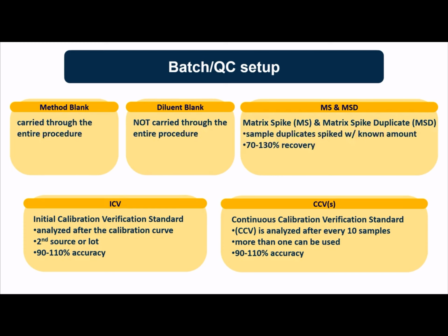So method blank, that's just simply carried through the entire procedure. Diluent blank, sometimes outside of metals may be called a solvent blank. So that's just your solvent or your diluent that's not carried through the procedure. A matrix spike and a matrix spike duplicate. So that would be a matrix sample that was spiked with a known amount, and you do duplicates of those. The suggested criteria for that was 70 to 130% recovery.